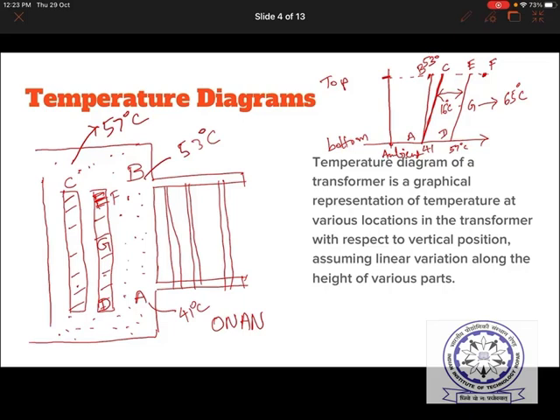So E is at 73 degrees centigrade, and F is the hot spot temperature, which is 75 degrees centigrade. So this is how the temperature diagram of a transformer will look. This is an ONAN transformer. The temperature diagram given here is of an ONAN transformer. Oil natural, air natural. It means the oil will circulate by natural convection only, through these pipes and then through the windings, and the air outside this cooler is also cooled by natural convection.